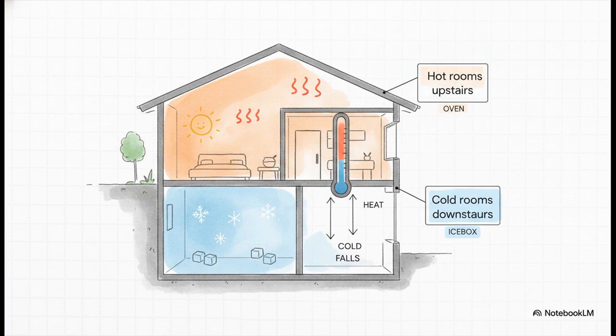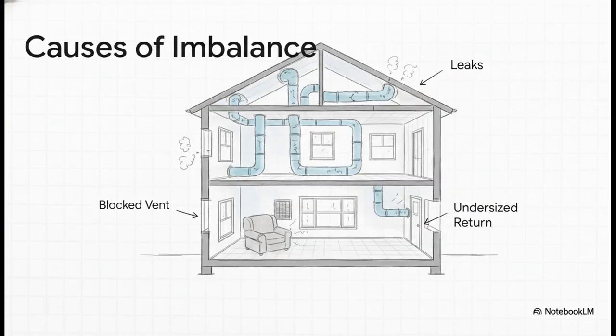So why does this happen? Well, it's almost never just one thing. The problem is usually systemic. The ductwork that's supposed to carry the conditioned air might be too small, or maybe it's leaking air into your attic. Vents could be blocked, or, and this is a big one, the return air system that's supposed to pull air back to the furnace isn't big enough, and that creates these weird pressure imbalances all over the house.